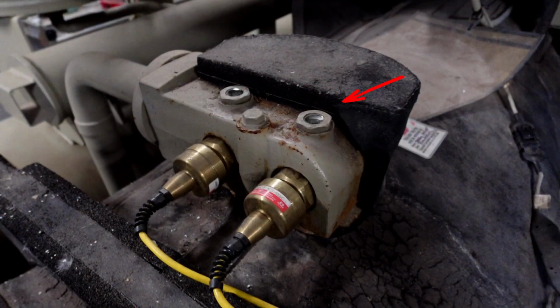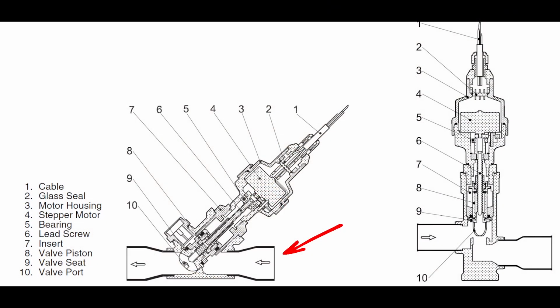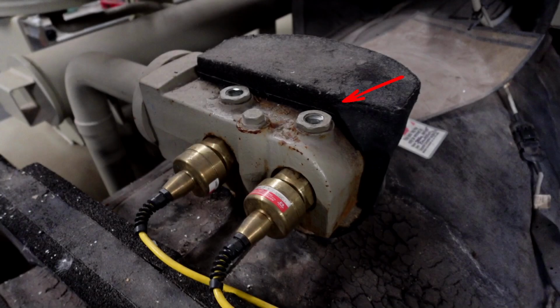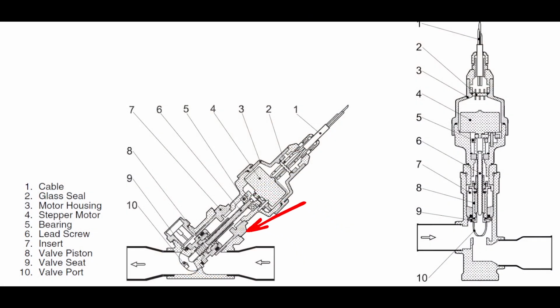One of the things that they'll do is, instead of having a block like this, they will have a regular body like this, but there'll be two of them. And you have the exact same issues you could have with a block style. It's just they'll have two of these run via tees. So your liquid line will come in and it will tee off, and then it'll go through two different sets of valve, or two valve bodies, and then it will tee back together as it enters into the evaporator. So as it's coming back into the evaporator, they'll tee back together.